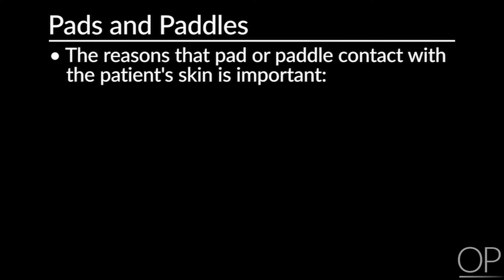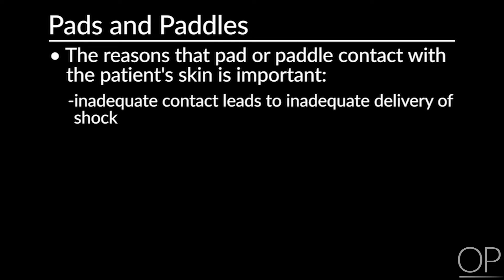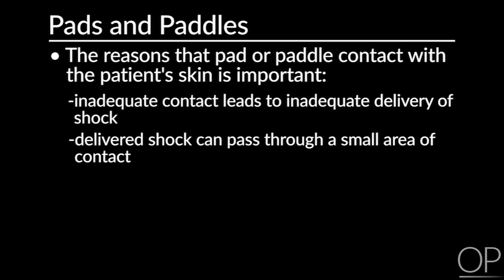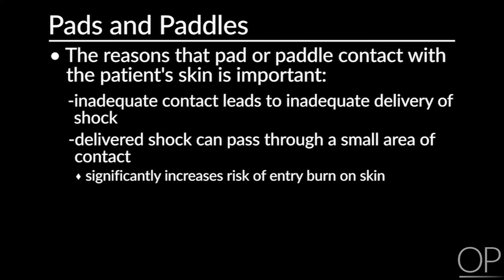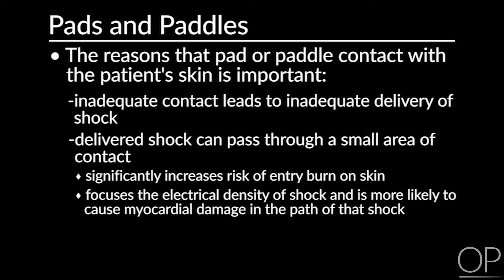The reason contact is so important is twofold. First, inadequate contact can result in the delivery of an inadequate shock. Second, if there is contact with only a small portion of the paddle or pad, the entire delivered shock passes through that small area of contact, significantly increasing the chances of an entry burn. Additionally, it focuses the electrical density of the shock and is much more likely to cause myocardial damage in the path of that shock.